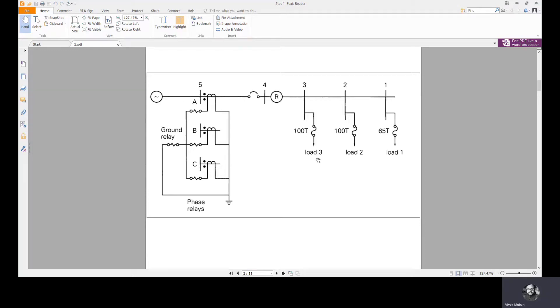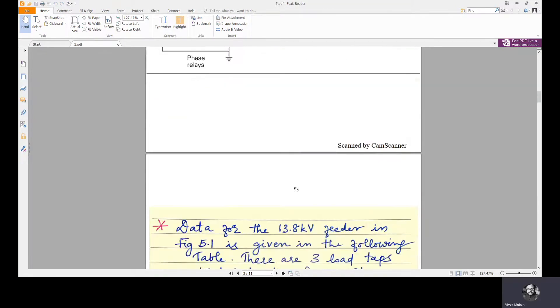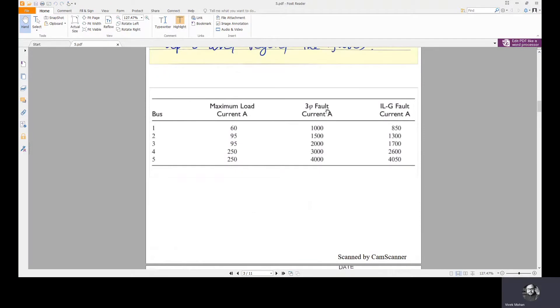The first fault under consideration is a self-clearing temporary fault — a three-phase fault on the load side of tap 2, that is this side. From the table given here, for bus 2, the three-phase fault current is 1500 amps. We have to find the first protective event that will happen after this 1500 amp three-phase fault has occurred.